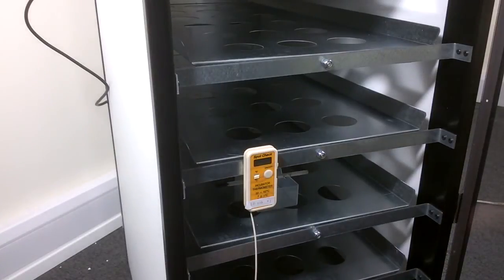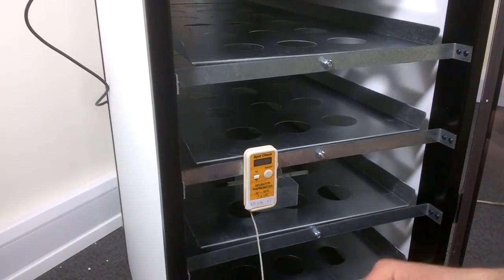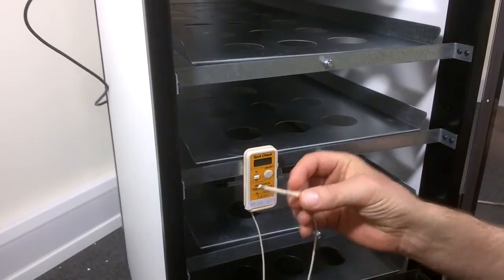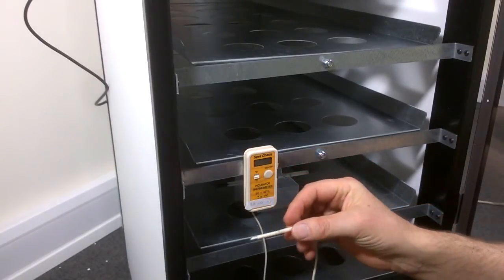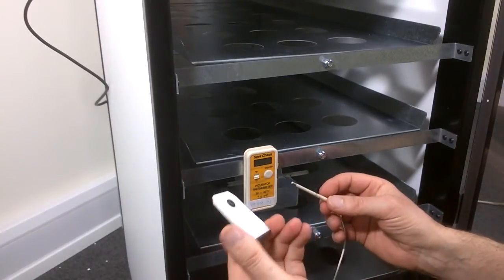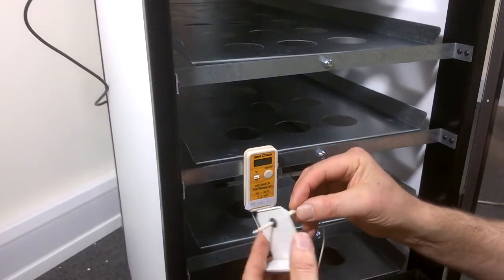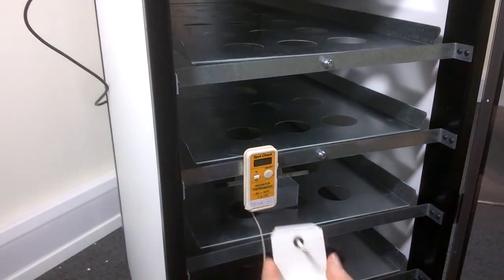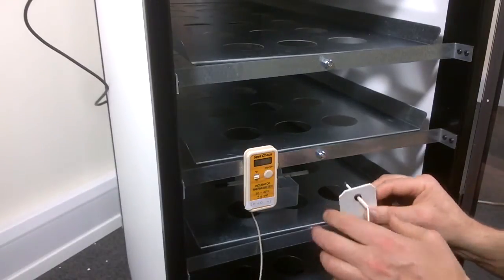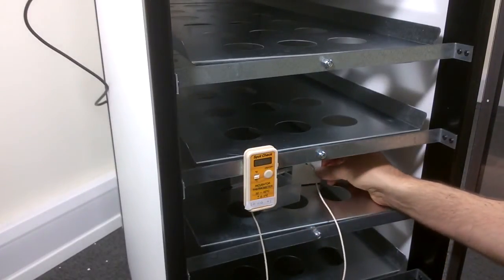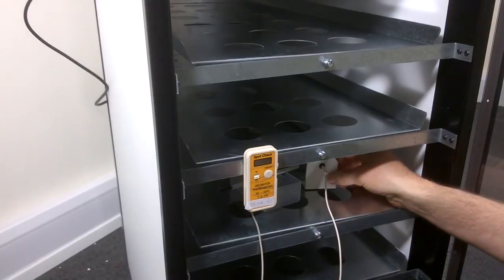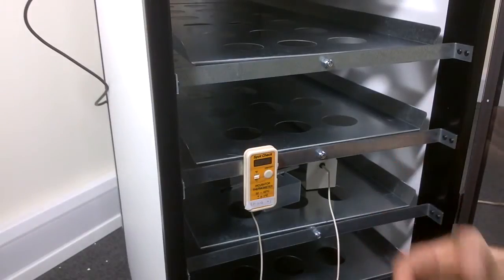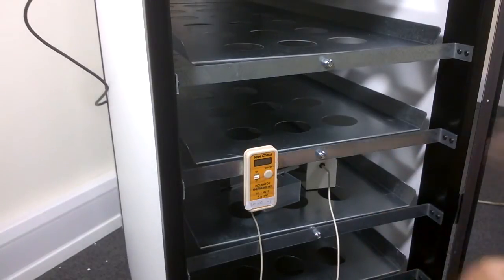What we then need to do is to place the probe of the thermometer at a height of 30 millimeters. Now what we do here is we have an ingenious little piece of kit here where we can put the probe through it and we can place that probe in here in the machine. So we can place that towards the center of the tray as we like, so that we can take a reading. I then close the door and I leave it for half an hour to stabilize again, and then I take that reading.